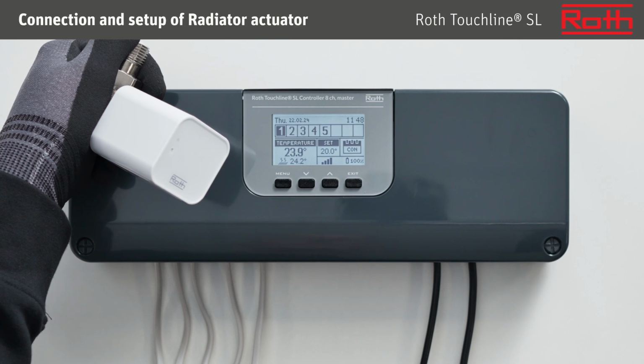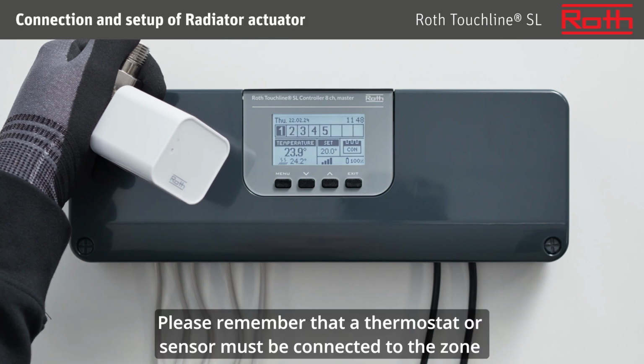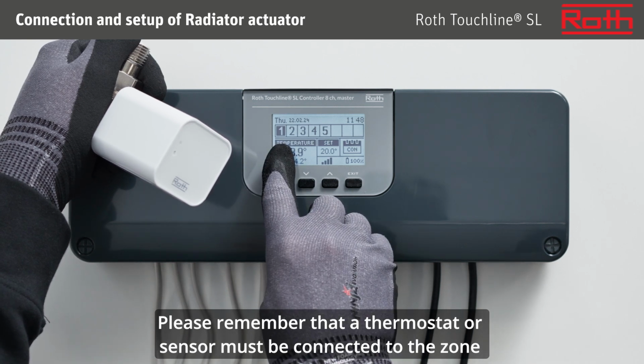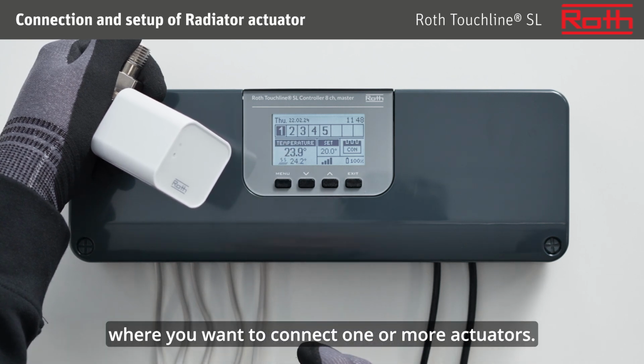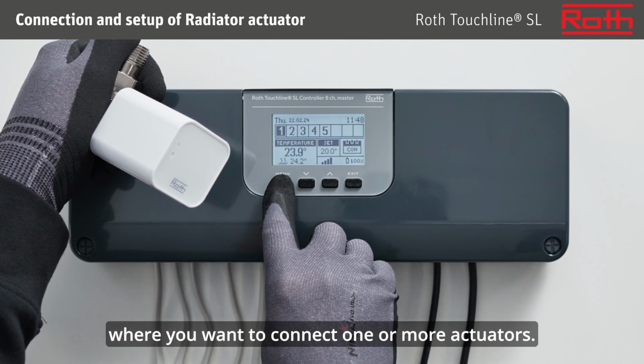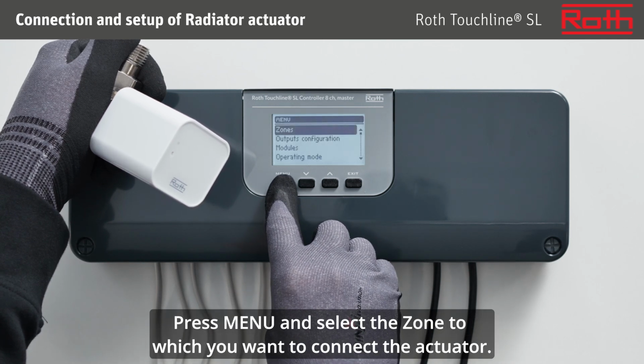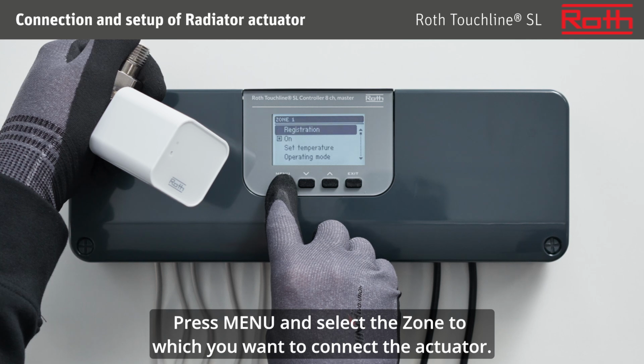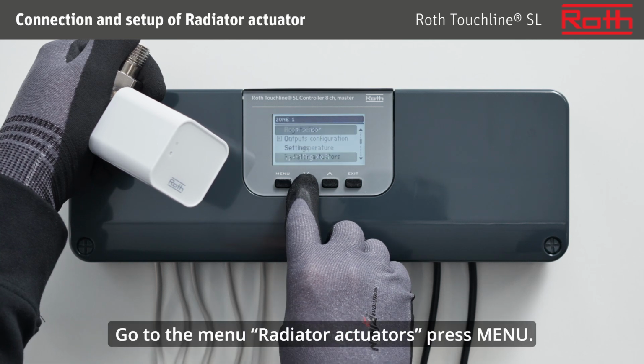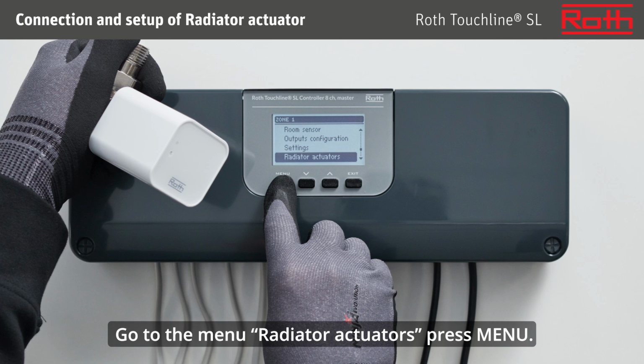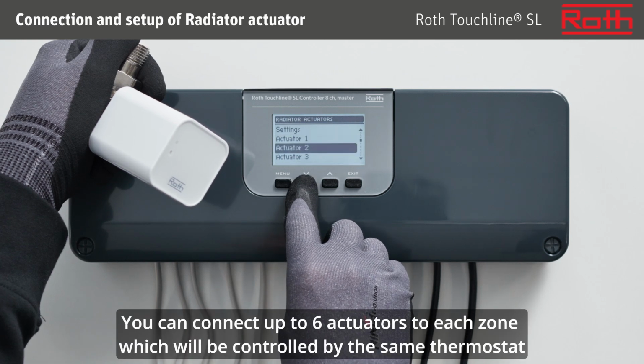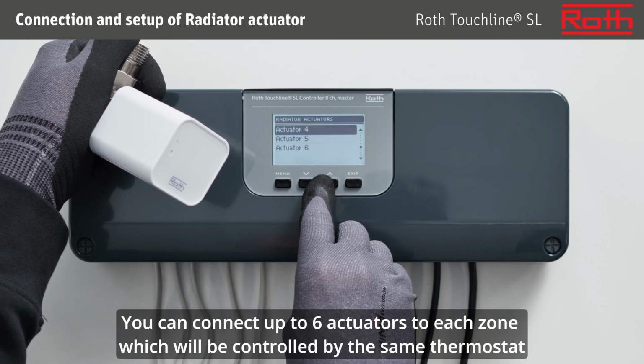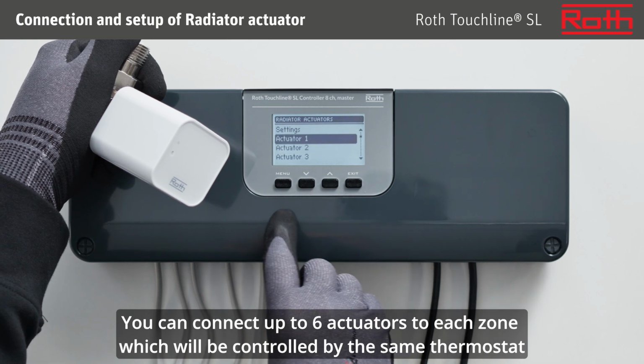Connection and setup of radiator actuator. Please remember that a thermostat or sensor must be connected to the zone where you want to connect one or more actuators. Press Menu and select the zone to which you want to connect the actuator. Go to the menu Radiator Actuators, press Menu. You can connect up to 6 actuators to each zone, which will be controlled by the same thermostat.